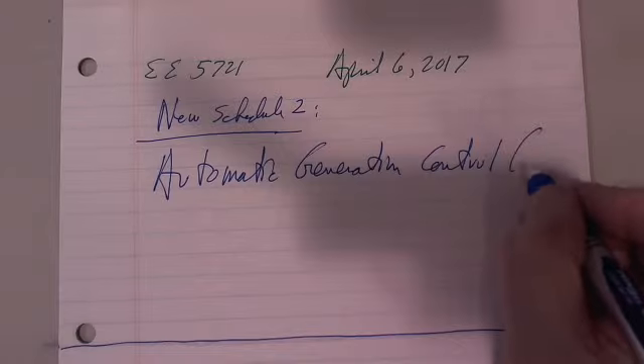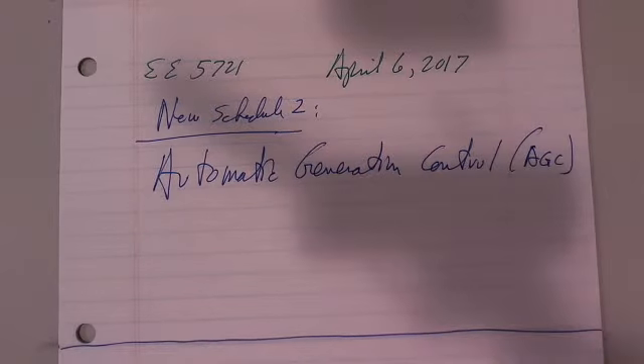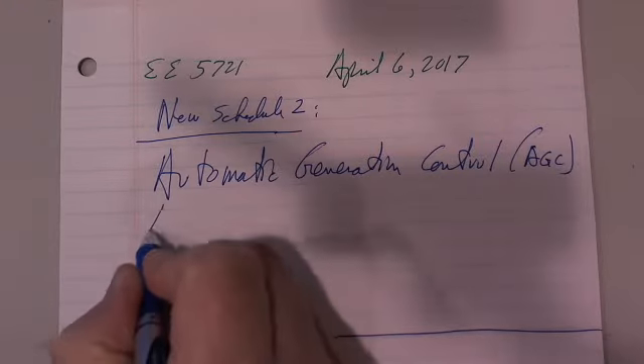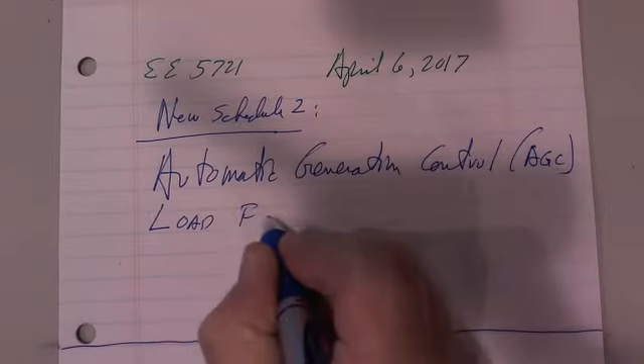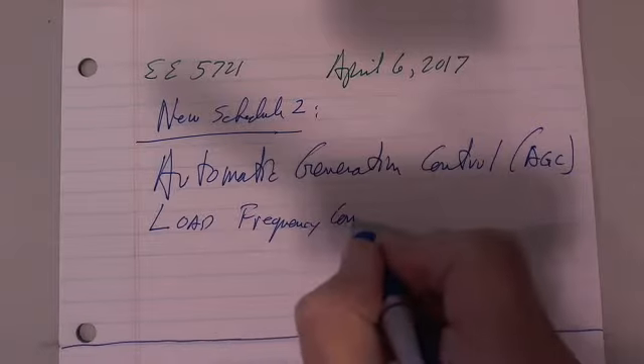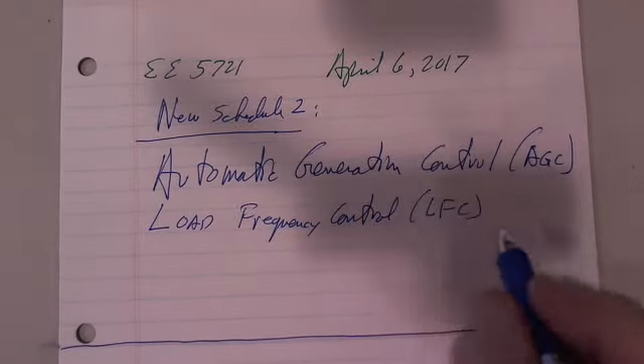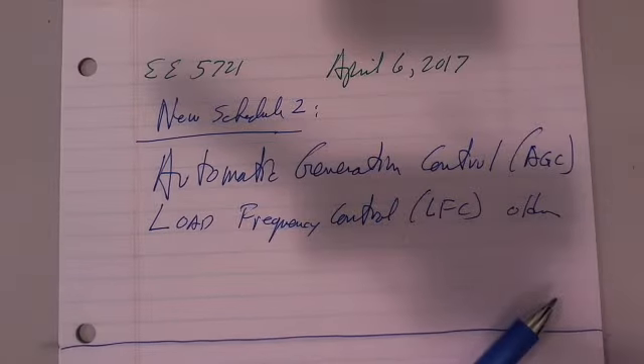This is the official, and of course it's abbreviated AGC. This is the official IEEE. You may see literature where you see the term load frequency control, or LFC. This was the older nomenclature. Some perfectly obnoxious wise guy probably pointed out the fact that we don't control the frequency. We control the generation in order to keep the frequency where we want it. And so, on that basis, they changed the name to automatic generation control, which is a little more accurate.